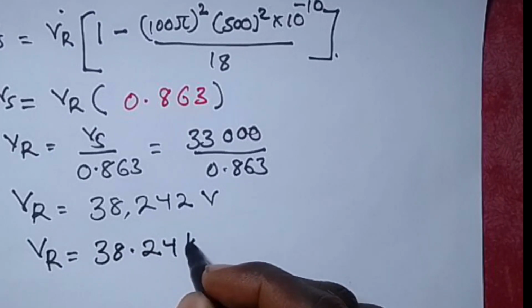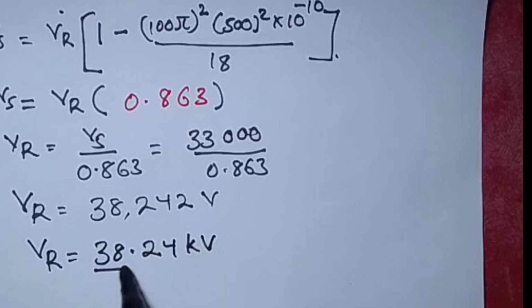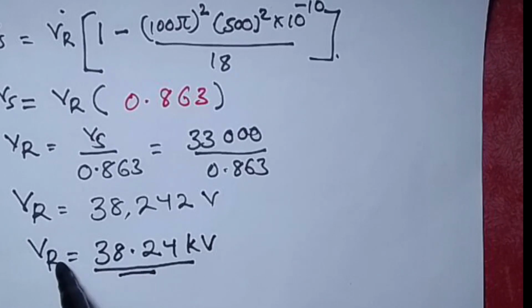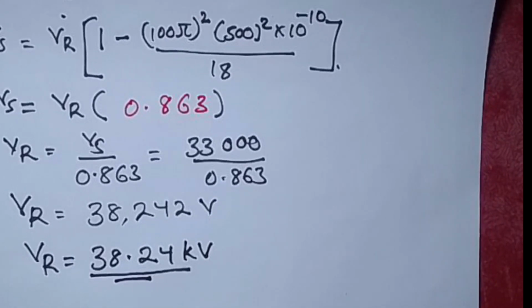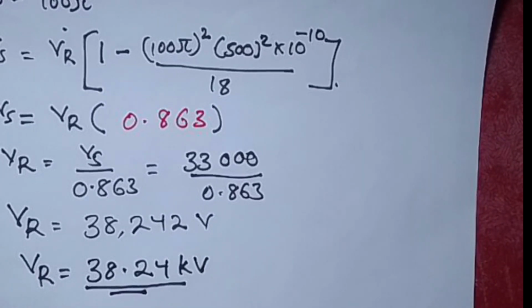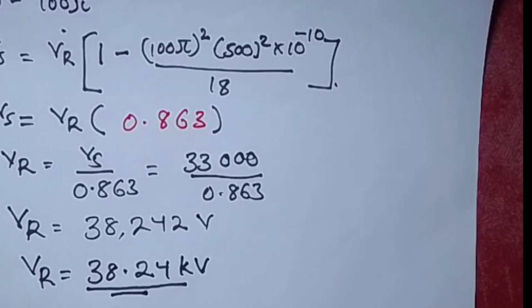So clearly, my engineers, you can see that the voltage at the receiving end is far greater than the voltage at the sending end. Remember that our voltage at sending was equal to 33 kV. So where does this extra come from, because 38 minus 33 gives us an extra of 5 kilovolts. All this extra kilovolts is an over voltage, and it will definitely cause harm to the receiving end.